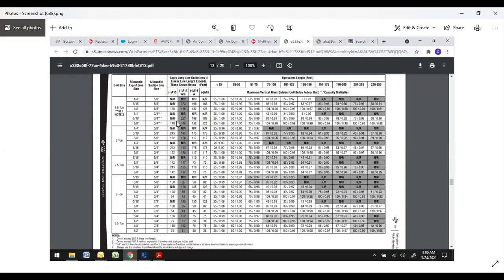And this is about the line set selection. If you sell jobs or if your service or installation, it is important to understand what you're dealing with, what's allowed. So you can come over here, if you're going to do a 2 ton, for instance, it will tell you what's allowed. So a quarter inch and 5/8, you'll see here it's not recommended in any of these models, but you could do it because you can come over here, 5/16, 5/8. You can come over here. Ideally, you'd want to do a 3/8, 5/8. You're good up to 75 to 100 feet. 3/8, 3/4. You'll see here, and 2 ton.